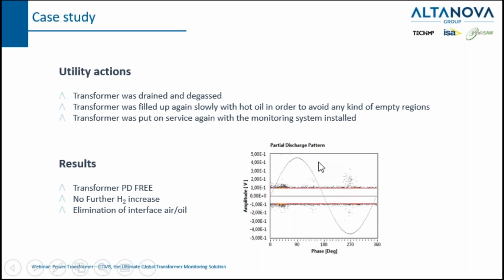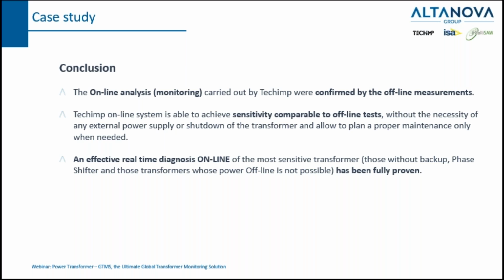You can see that the transformer was now completely PD free. No other increase of H2 was recorded by the DGA unit. And then you can also see from this RPD that only noise is present. So we also eliminated any problem with the interface in air and oil. So the conclusion of this experience was very, let me say, positive for the end user and also for us. We reached a sensitivity comparable with the offline test. It is very important, this point. And also this kind of approach, the real-time and online global monitoring system, its benefit has been fully proven with this kind of activity.